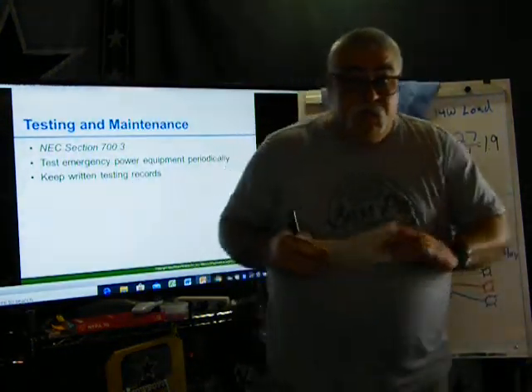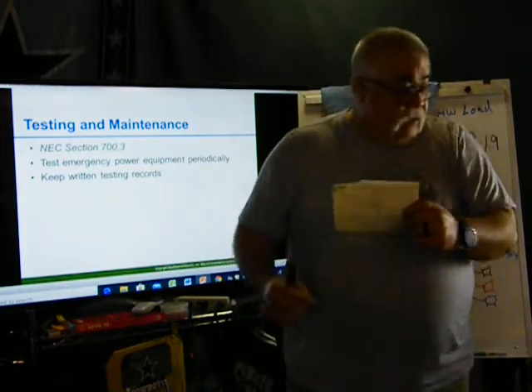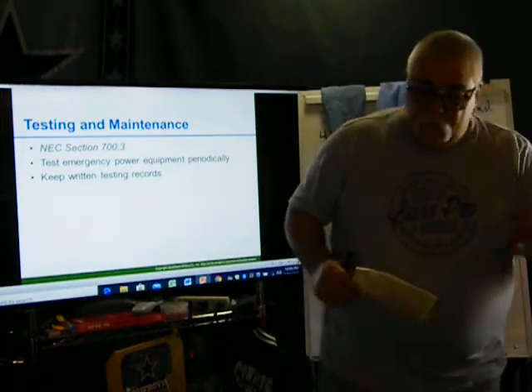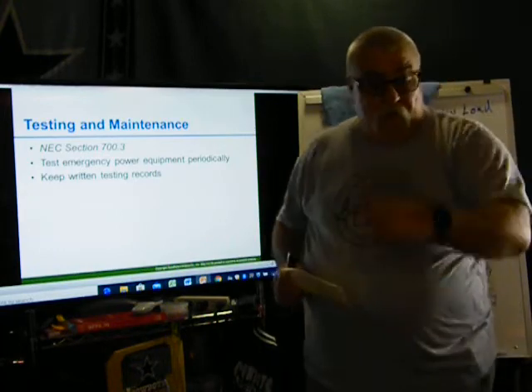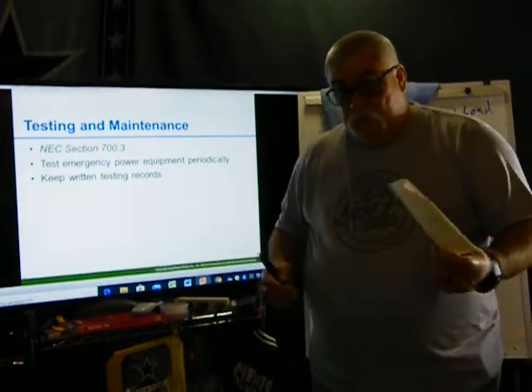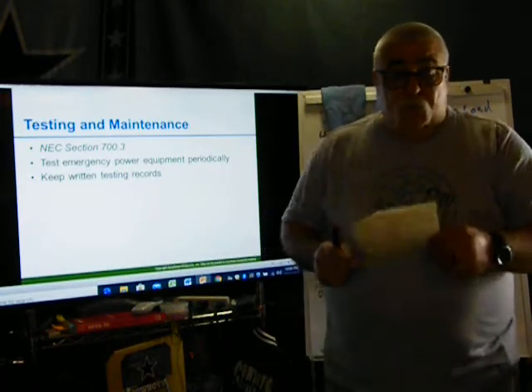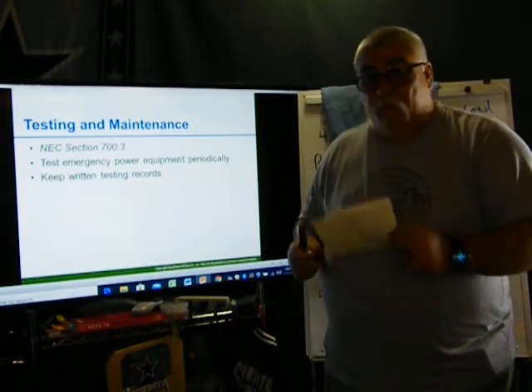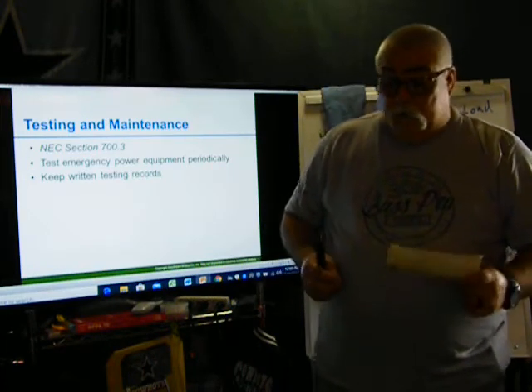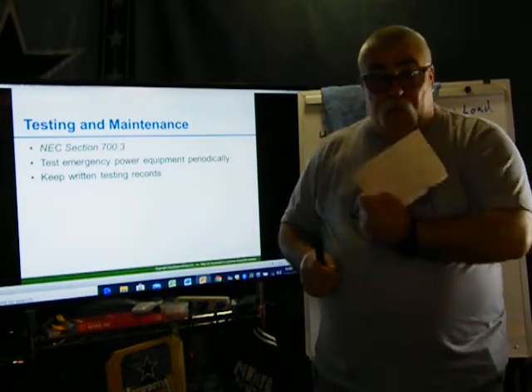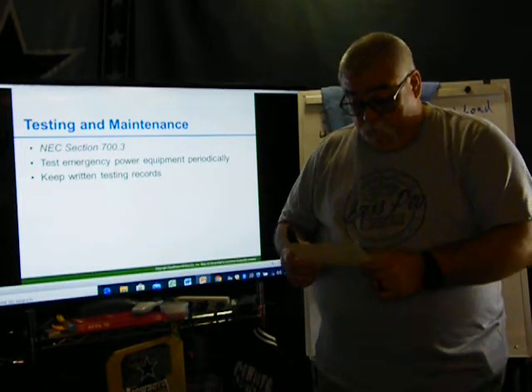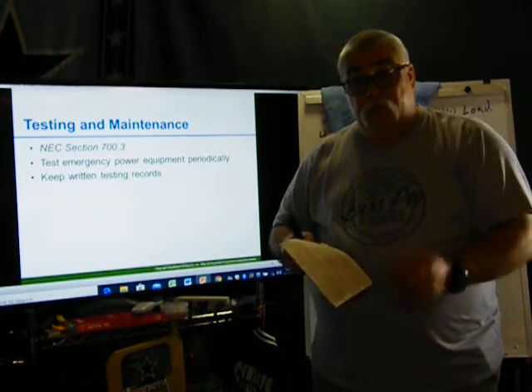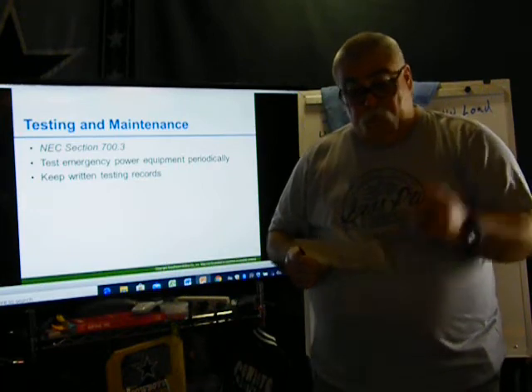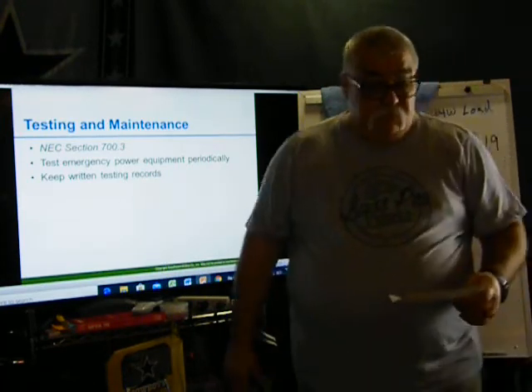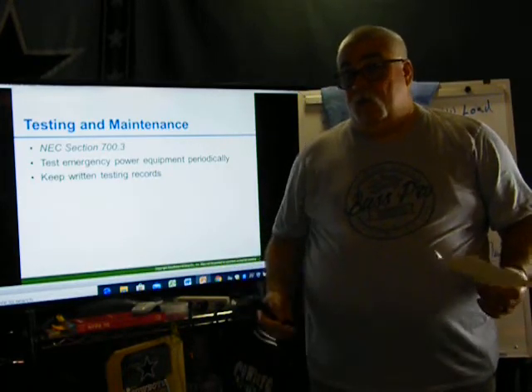The code tells us to follow the code on, what was it, 100 and, I drew a blank on that, 103 I think. Well, it says for installation we install it according to the manufacturer's instructions. Guess what? For maintenance and everything else, we also follow the manufacturer's. An inspector may come in and change that, but at least we have a blueprint for what we've got to do. So this one says every 30 days, test it for 30 seconds. And once a year, test it for the whole duration, 90 minutes, which is an hour and a half. Okay, if it doesn't stay on for an hour and a half, you've got to change them out.